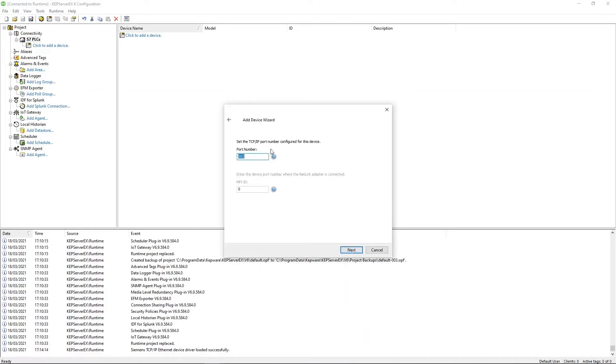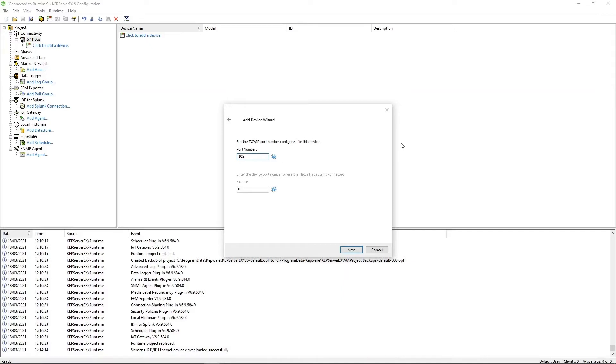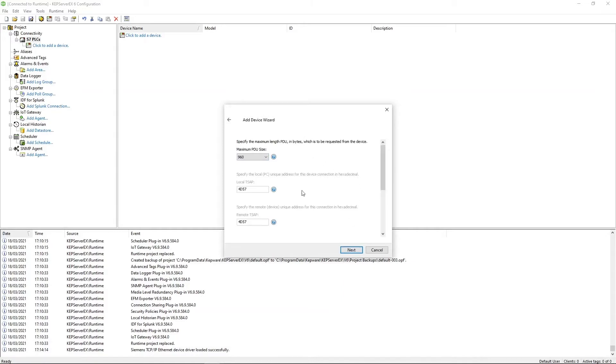Here you choose the port number. The default for S7 devices is 102, or if you're using Netlink, it's 1099. And these will typically be the ports you use to communicate with the S7 device. But if you're going through maybe like a firewall or some specific network configuration that requires you talk to something else in between, you might need to change this port number. But in general, it's going to be 102. Next.